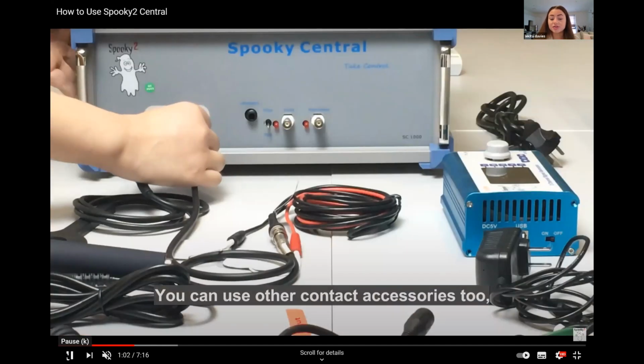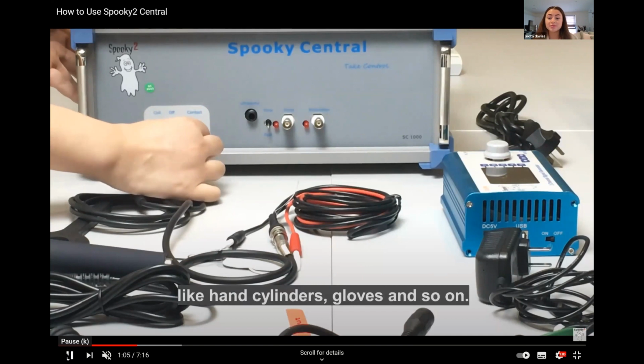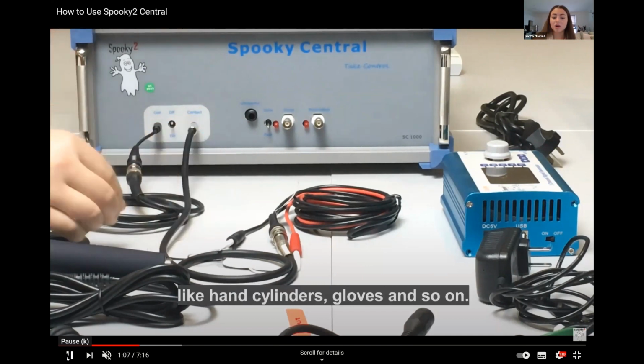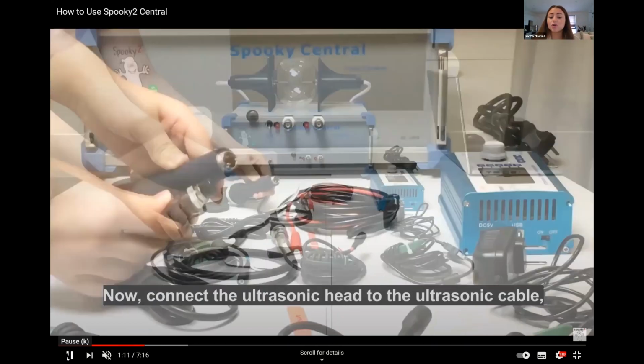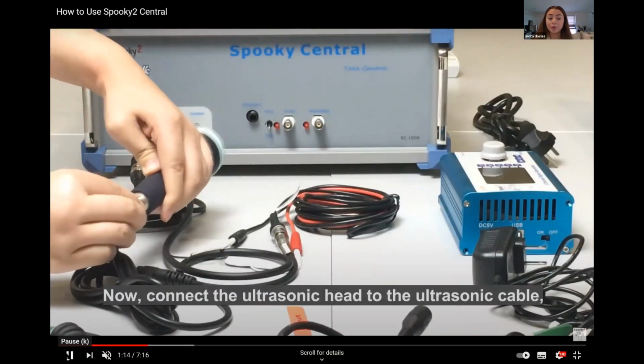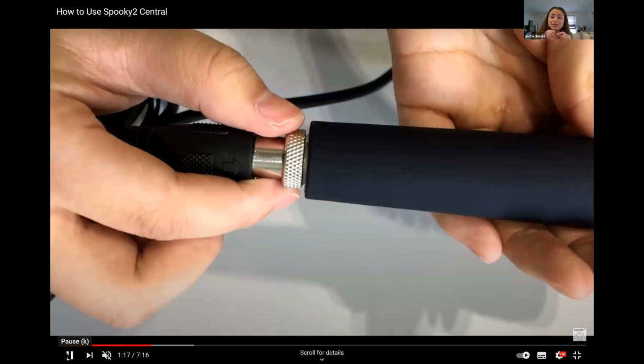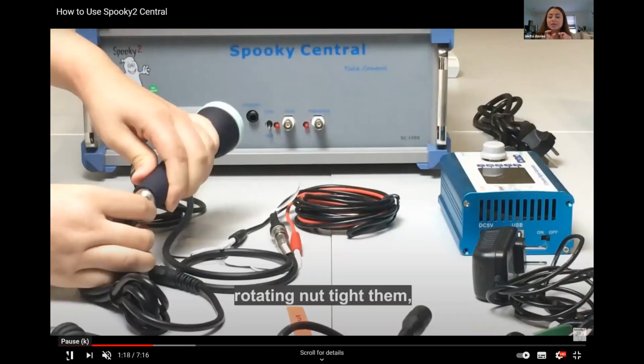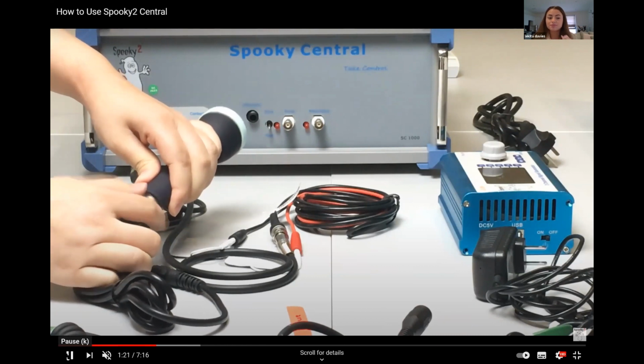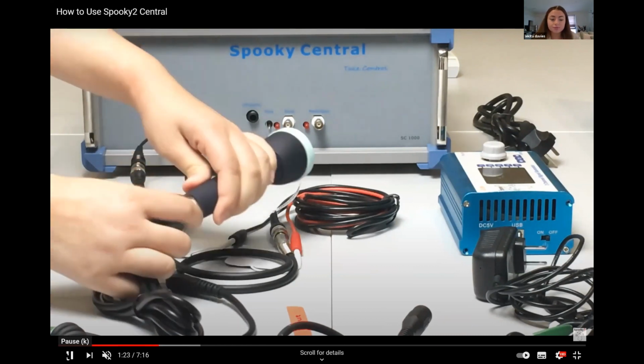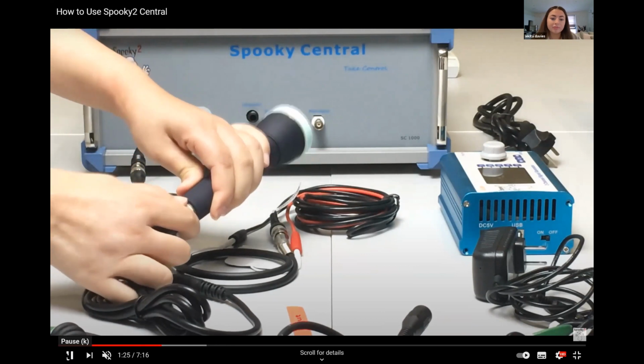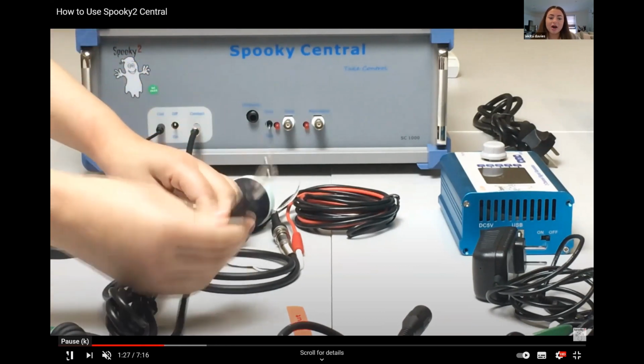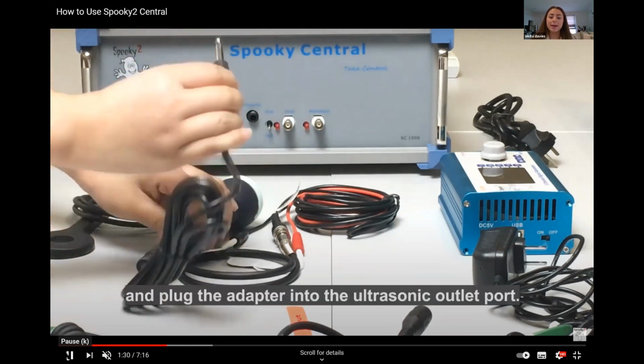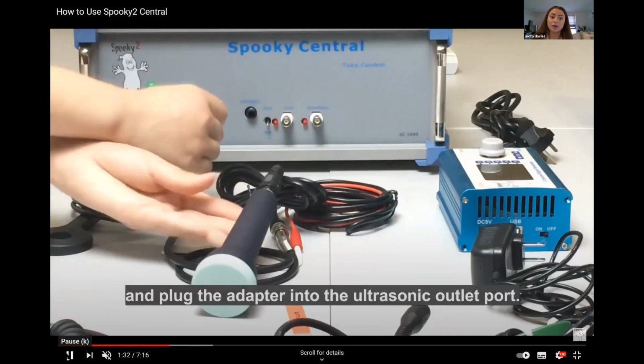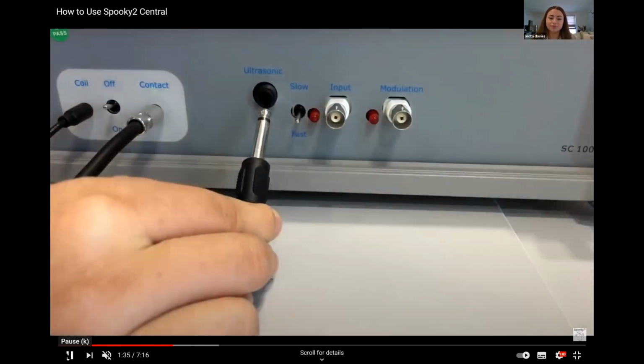She said you can use the other contact accessories too. That's absolutely fine, but contact pads just might be a bit easier. Then you would connect the ultrasonic head to the ultrasonic cable provided, twisting it so that it's tight and secure and won't come loose. Then take the other end of the cable and put it in the ultrasonic outlet port of the Central.